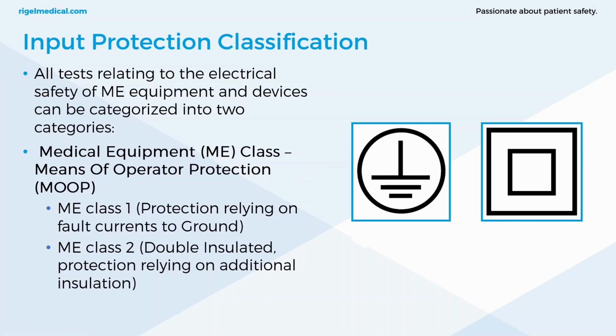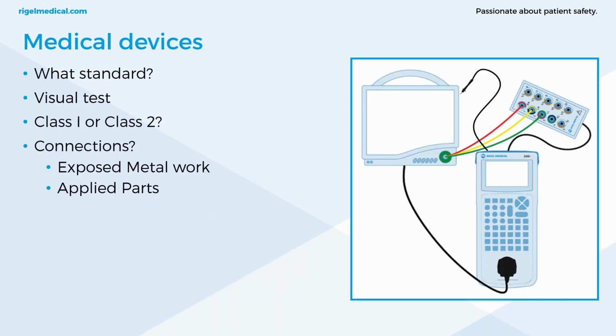To carry out an electrical safety test, normally at first face value, you'll know what to perform. So when electrically safety testing a medical device, first you need to know what standard. You might be using a type test standard like 60601, or your recurrent testing type standard or code such as NFPA 99. You'll be carrying out a visual test. Now this is things like housing defects, chassis cracks, correct fuse ratings, etc.